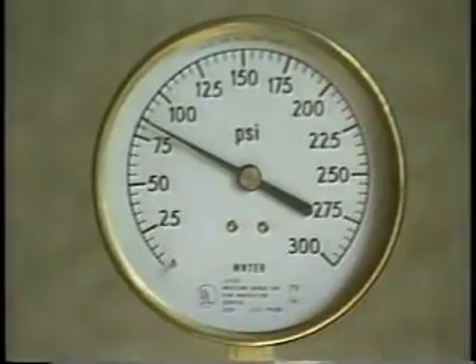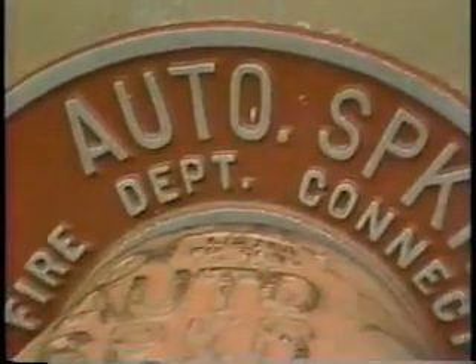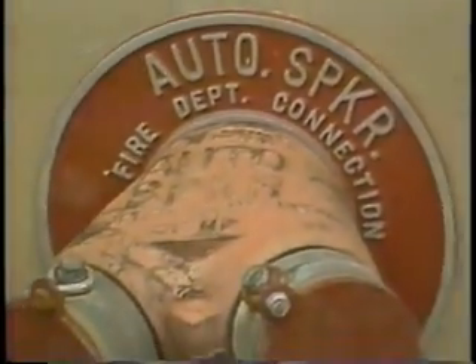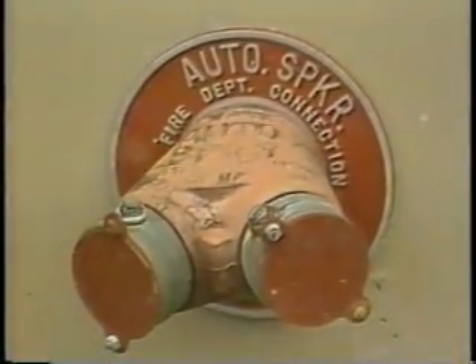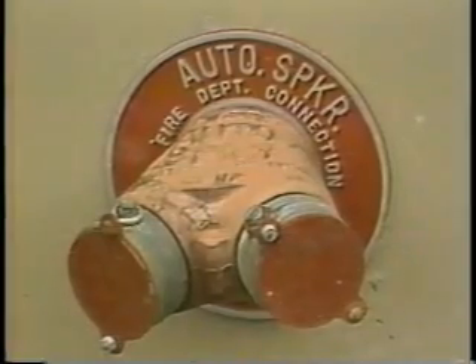These systems may be dry or charged with water. Heat from the fire melts a fusible link which allows water to spray from the system onto the fire. Connections are often provided for a pumper to couple into this system to provide water pressure and volume support throughout the sprinkler system.